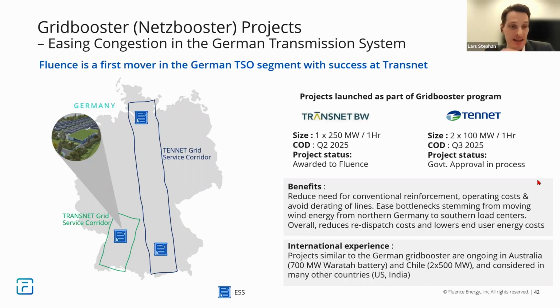Using batteries within the transmission grid as a transmission asset, we change this paradigm and we move this contingency element onto the battery. This means now we're utilizing the transmission line to its fullest capacity. And if a contingency event was to occur, those batteries, which are called grid boosters, will react within 150 milliseconds and start charging on the one side and discharging on the other side of those corridors. So reacting really, really quickly to contingency events in the grid, and thereby preventing us from keeping transmission line capacity underutilized. So this is really the whole trick of it. What that means in turn is, of course, that we have existing transmission lines, we can increase utilization, which directly translates into less congestion, and less curtailment of renewable energy that happens in Germany on a large scale.